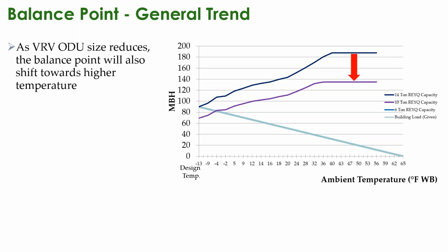So take a look at your options, and in this option we're looking at a 6-ton, a 10-ton, and a 14-ton. Your 10-ton, your balance point is at that minus 4 area. If you went to a 6-ton, if it covered your cooling load, the juice may be worth the squeeze, depending on what your auxiliary heat source is, to go to that smaller capacity outdoor unit and move your balance point to a higher position there. In this case, it's about 10 degrees. So not adding a whole lot of extra heat at that point, but reducing a lot of upfront costs.